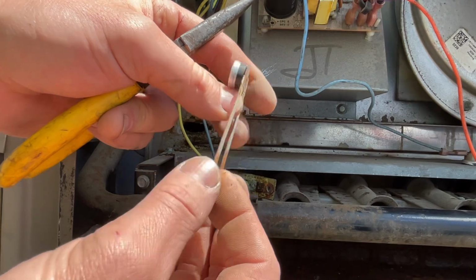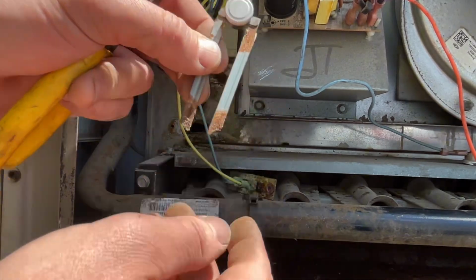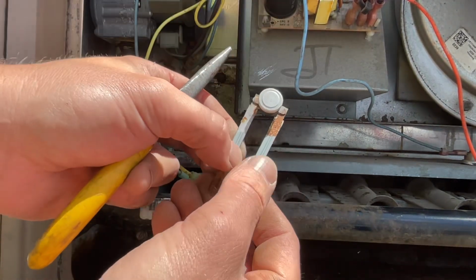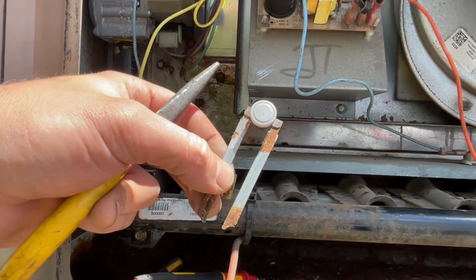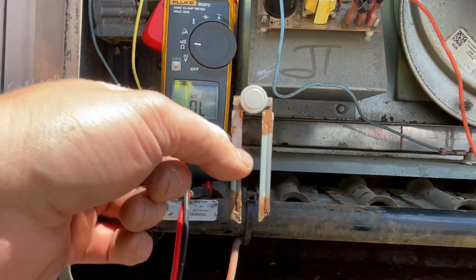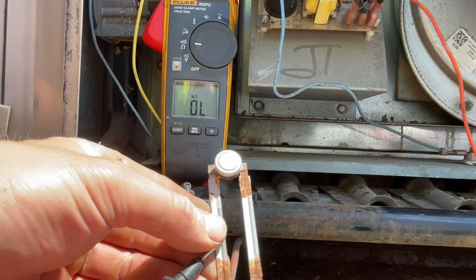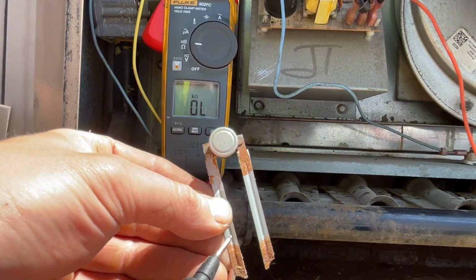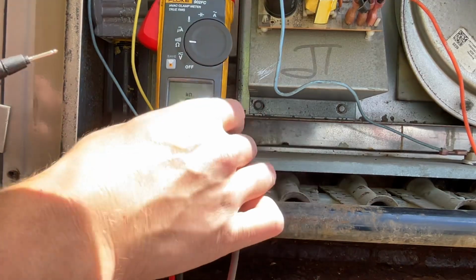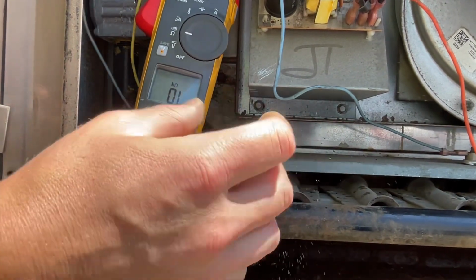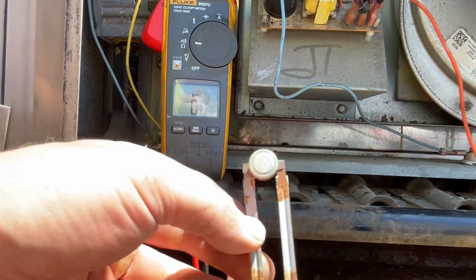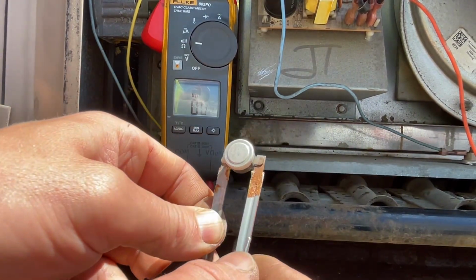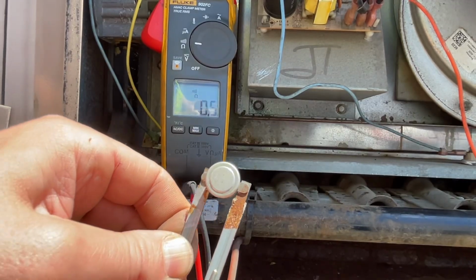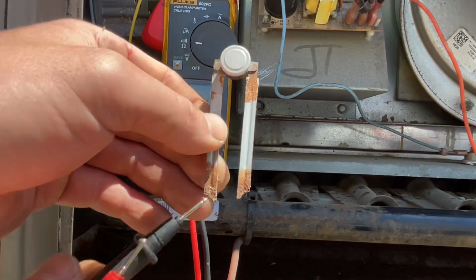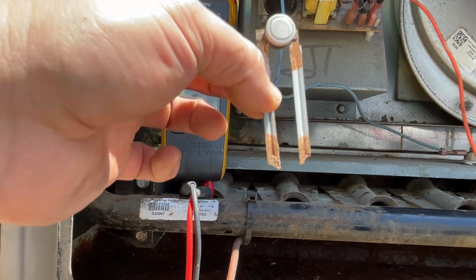And I'll show you now how to ohm one of these out if it was still in, full contact. We can still ohm it through these little arms. Let's do that. All right, so here's what's left of that limit switch anyways, but these arms here, they just carry the voltage through our main part of our limit switch, which is right there, going into these terminals and therefore making our heating safety circuit. So if I was to put a lead here on resistance or continuity and here, you can see that our thermal disc itself is still good. It's just our connection point is cooked. So we're gonna need a new one of these.